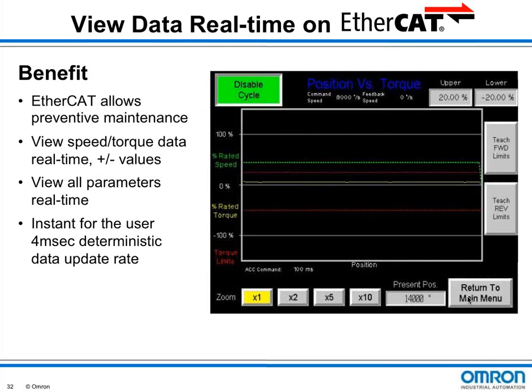Instead of waiting for a catastrophic event, operators can check the trend once a week. When mechanicals start to wear, an alarm can alert the team — not necessarily shutting down the line, but flagging an issue so it can be addressed during third shift or on the weekend before it becomes critical. The customer also asked about servo problems that occur after a year or more, when personnel may have forgotten the system. Keith's team developed a solution where all error codes were programmed into the HMI so that when anything happens, a descriptive message pops up with step-by-step repair instructions with pictures.